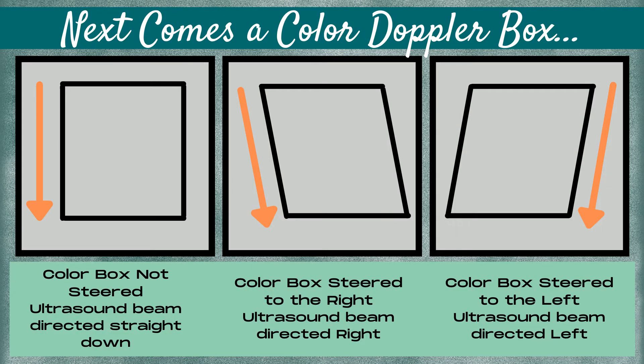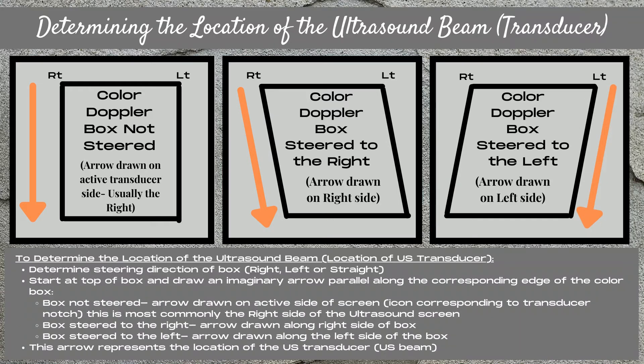The next step in determining direction of flow with Doppler is the color box. The color box populates onto the screen when the color Doppler control is turned on. The color box can be unsteered, meaning the ultrasound beam is directed straight down into the tissue, or it can be steered to the right or to the left. To determine the location of the ultrasound beam, you first need to figure out: is your color box steered?